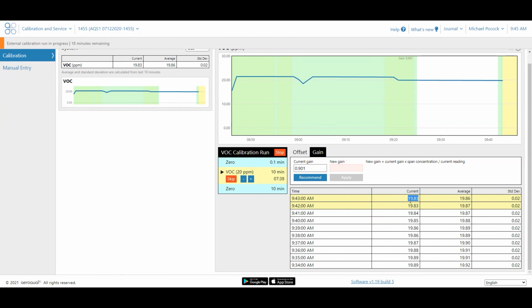But because I'm within that plus or minus 1 range, there's no need to change the gain. Just like with the offset, if you're within plus or minus 1, there's no need to change the offset. You're better off leaving it as it is. So, okay, stable reading, low standard deviation. We are satisfied that we've calibrated this at our span concentration of 20 ppm.